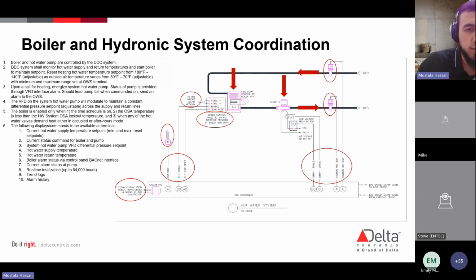The boiler is enabled only when the following conditions occur: the time schedule is on, the outside air temperature is less than a specific set point. It's right here. There's your outside air temperature. And when any of the hot water valves demand heat, either in occupied or after hours. This valve is, again, not shown here, somewhere down the building supply line. And if it calls for heating, that's when the boiler will turn on, right? So that's how a general sequence of operation builds. It depends on need, depends on how you want to control the system efficiently, and it depends on what the heating supply looks like in the building.